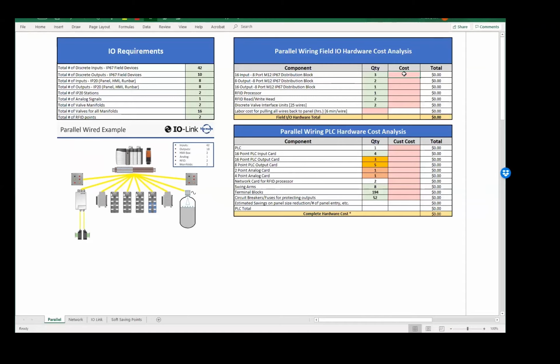I'm in the field of 16-point input IO blocks here for inputs. So we had 42 total IP67 inputs. Obviously we need 3 of the 16-input blocks to cover that. Okay. And we're going to say probably an average cost with that being a 16-point input block with a quick disconnect home run cord on there, maybe an M23 19-pin home run cord, of about $250. All right, perfect. I'll put that in. So the 8-output block we're not going to use, so we're going to zero out the cost on that. Okay. We can handle our 10 IP67 outputs with one 16-output block. Same price? Yeah, same price roughly.